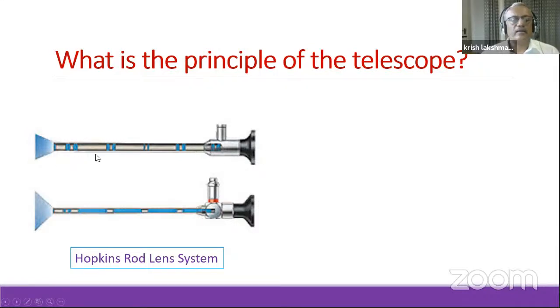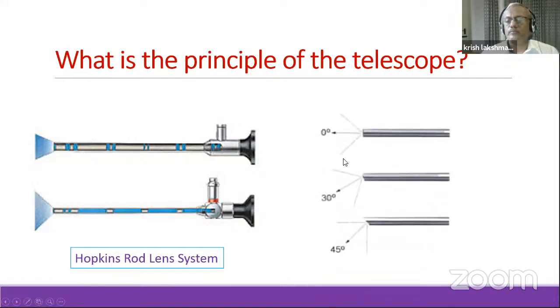It has got a solid lens system, solid glass like this. And if you want to bend the light either at this end or that end, for example to make it a 30 degree or 45 degree as you rightly mentioned, then you have to use prisms to bend the light. But it is not the fiber optics used in a flexible endoscope. Can you see this? This is 45 degree and this is 30 degree. What does it mean to you - this 0, 30, 45 - what does it actually mean?